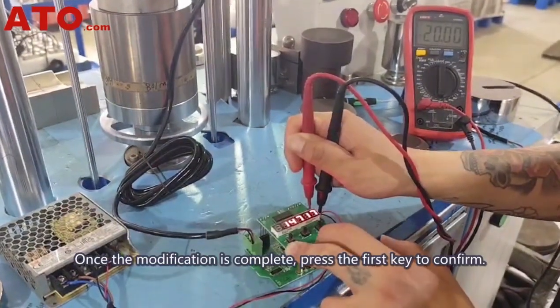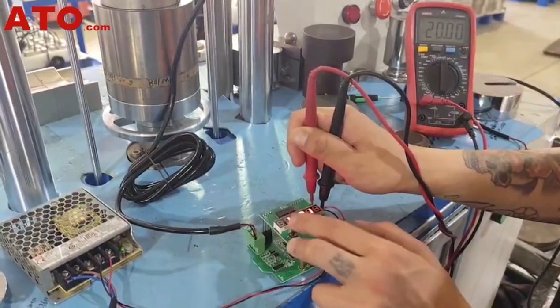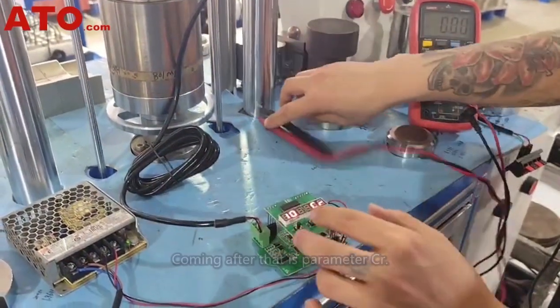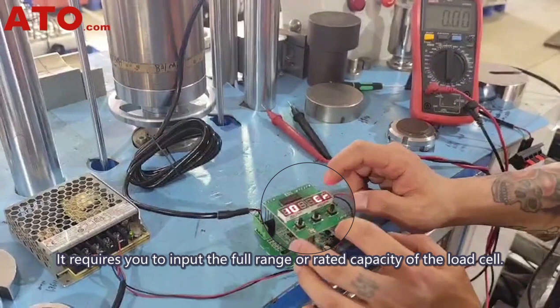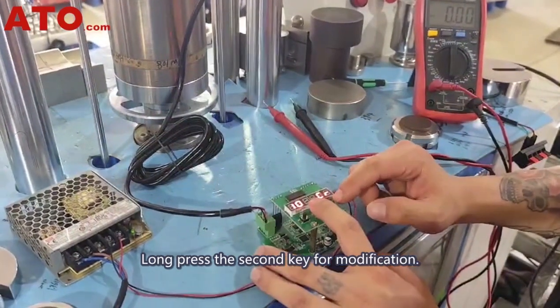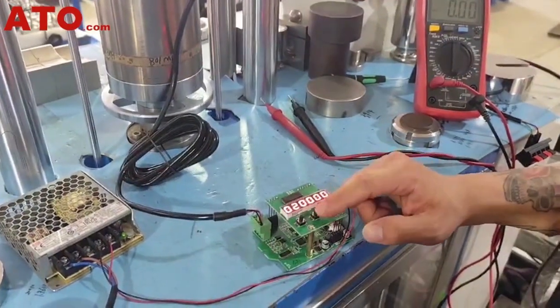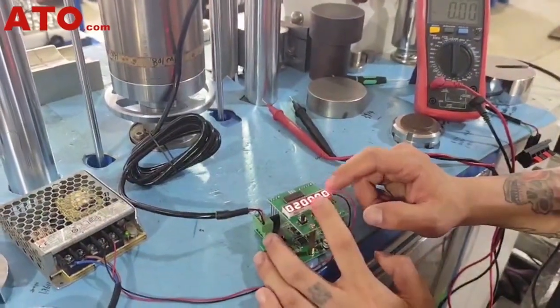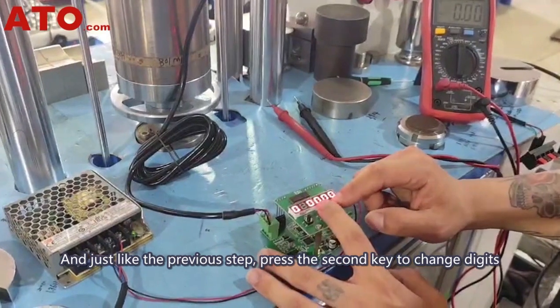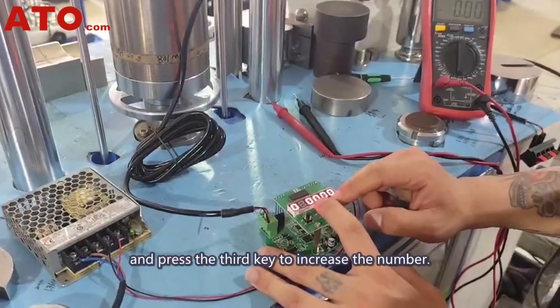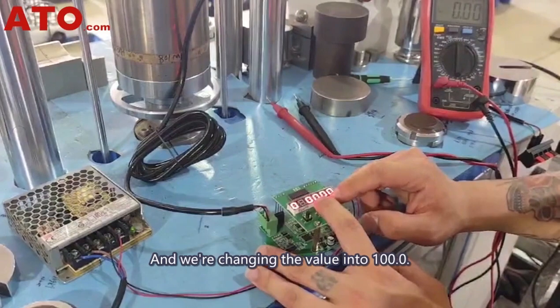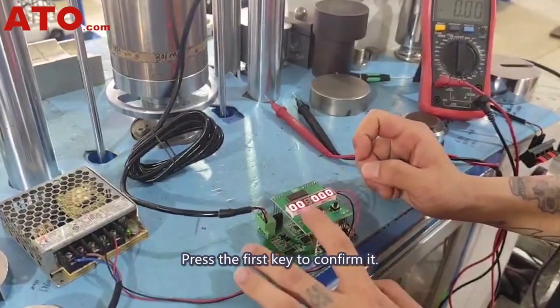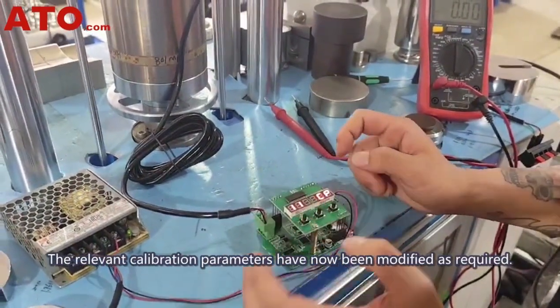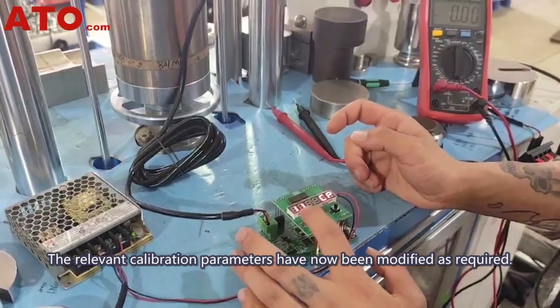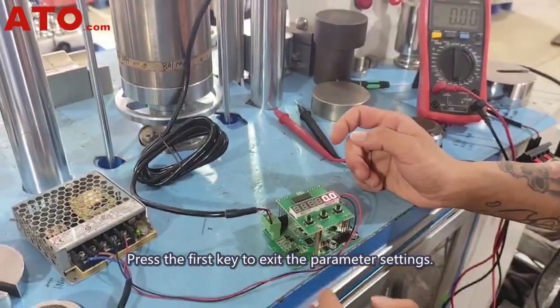Once the modification is complete, press the first key to confirm. Coming after that is parameter CR. It requires you to input the full range or rated capacity of the load cell. Long press the second key for modification. And just like the previous step, press the second key to change digits, and press the third key to increase the number. And we're changing the value into 100. Press the first key to confirm it. The relevant calibration parameters have now been modified as required. Press the first key to exit parameter settings.